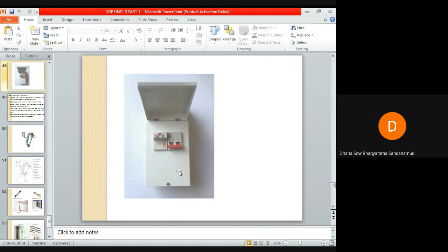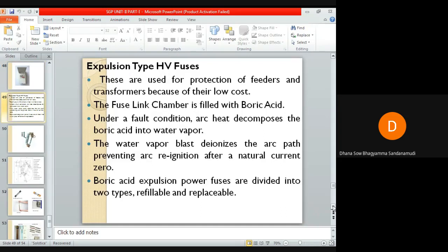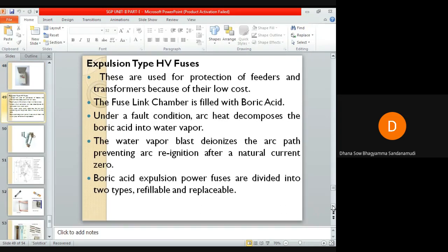These fuses can be used for very high voltage circuits and operate more satisfactorily under short circuit conditions approaching their rated capacity. Actually, this topic is not required as per your syllabus, but I thought it will be useful for you to know about this fuse also. The rated voltage levels of the metal clad fuses are 5 kilovolts and 38 kilovolts. And the next type is the expulsion type HV fuse.